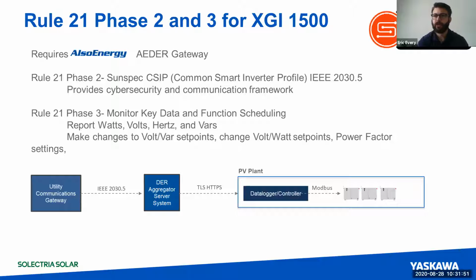If you're trying to maintain frequency and voltage and keep the lights on for everybody, and you have a resource that's up and down all day, every day, all your protection functions are firing faster than they should be. The control systems in place are designed to look at things over the course of maybe a 15-minute span or an hour-long span.